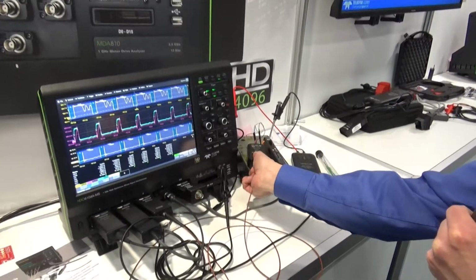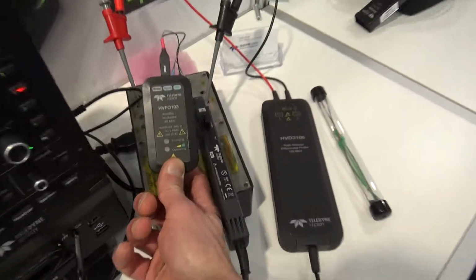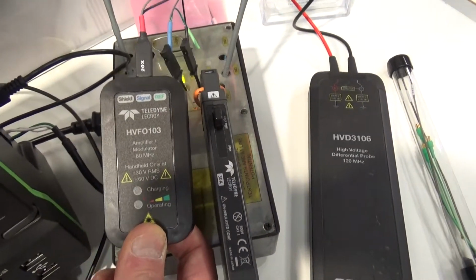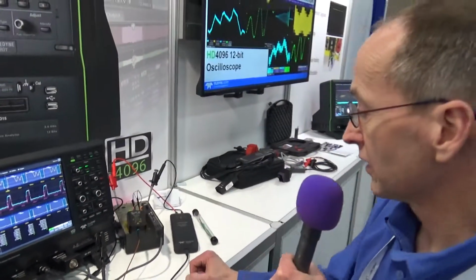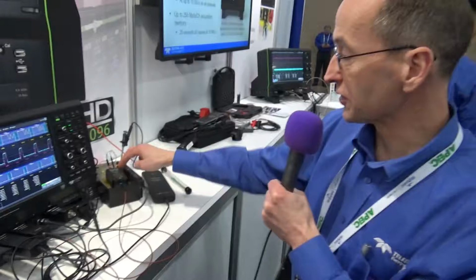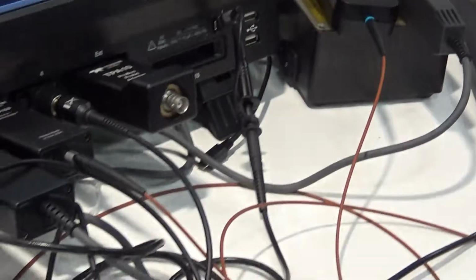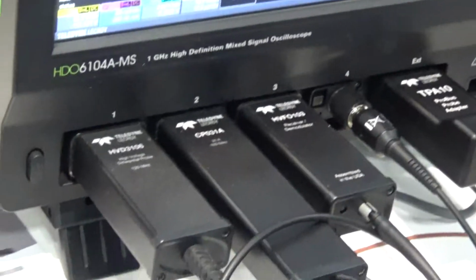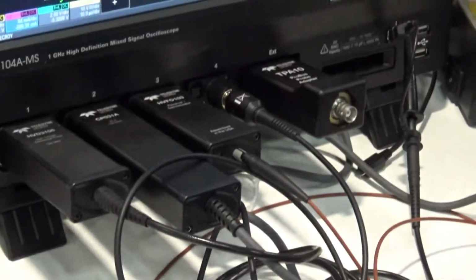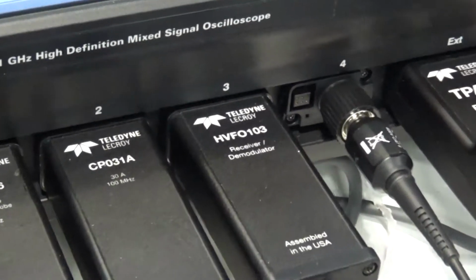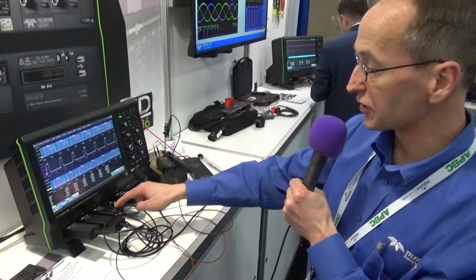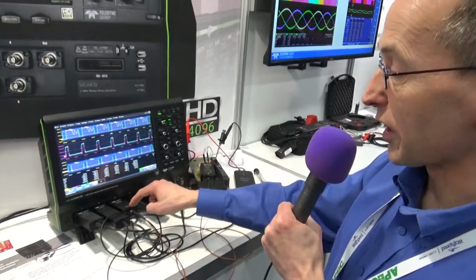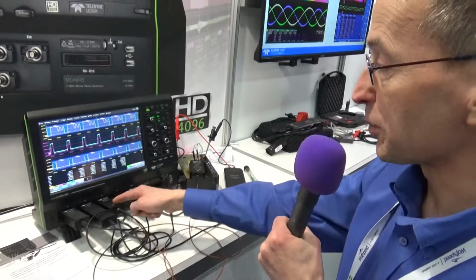This is our high voltage fiber optic probe. It's called the HVFO 103. This is rated for 60 megahertz. It's fiber optically isolated, so it has a nominal 35 kV fiber optic isolation to ground. This is the transmitter. Optically, it transmits out. There's a tip that'll measure the small signal riding on top of a floating high voltage signal. It transmits that fiber optically. This is battery powered, so that's why it can be that high up above ground. This is a fiber optic link right here that can be purchased in tens of meters of length if necessary. And then this is the demodulator, optical to electrical demodulator. That goes to the input of the scope and displays the signal on the scope.